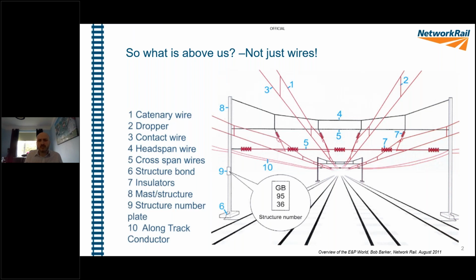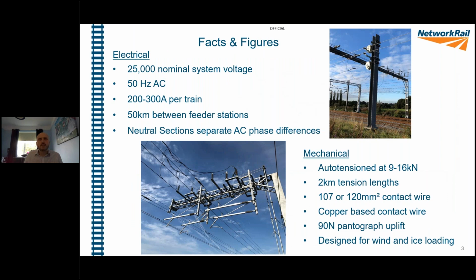So if we go over to the next slide, please, Gareth. Just a few facts and figures. The nominal system voltage is 25,000 volts, 25 kV in the UK. You will see light rail systems that have a lower DC voltage. Our system now is all 25 kV AC, 50 hertz system. That's the supply frequency in this country. Electric trains running on the system tend to draw between 200 and 300 amps. Our standards cap single train current at 300 amps, but we do have some exceptions. For example, an 11-car Pendolino will pull about, I think it's 307 or 309 amps, and there is a derogation in place to allow that.